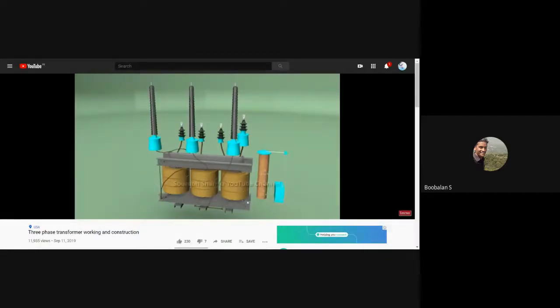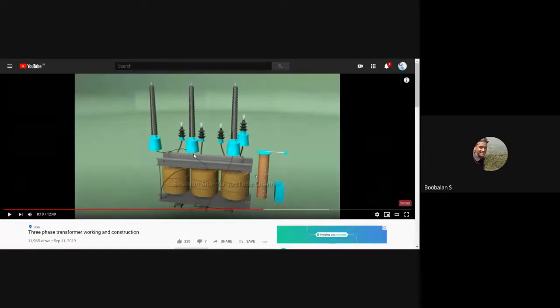In most models, this tap changer is installed within the transformer. This type of tap changing transformer is used to change the number of turns associated with the primary side as well as the secondary side. In a DC generator or DC motor, we cannot change the number of poles, right? It is fixed while manufacturing. In a transformer, we have one option, that is called on-load tap changing.